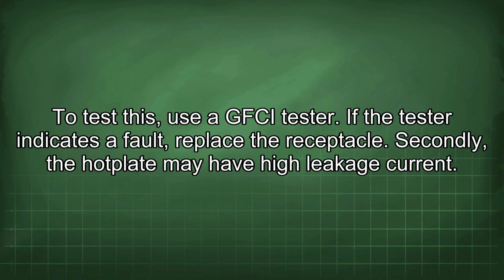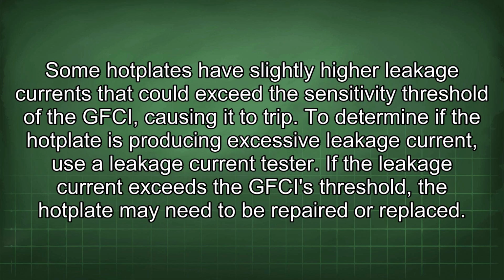Secondly, the hot plate may have high leakage current. Some hot plates have slightly higher leakage currents that could exceed the sensitivity threshold of the GFCI, causing it to trip. To determine if the hot plate is producing excessive leakage current, use a leakage current tester. If the leakage current exceeds the GFCI's threshold, the hot plate may need to be repaired or replaced.